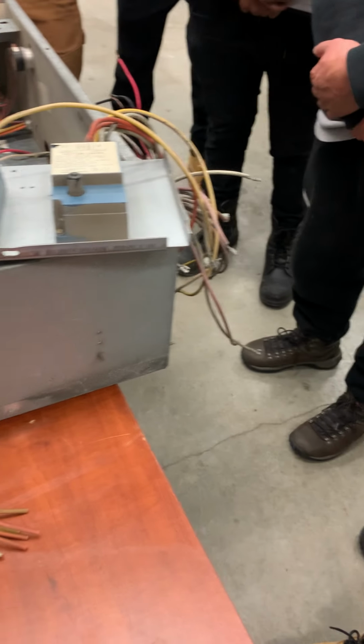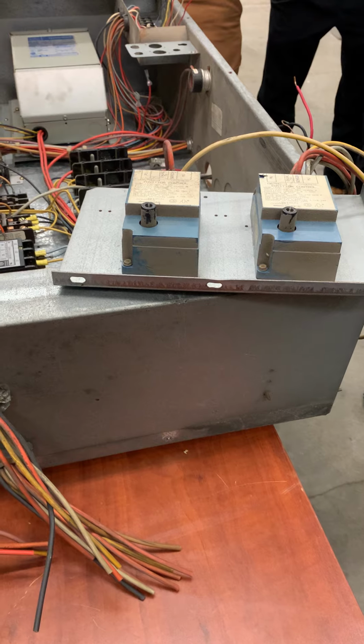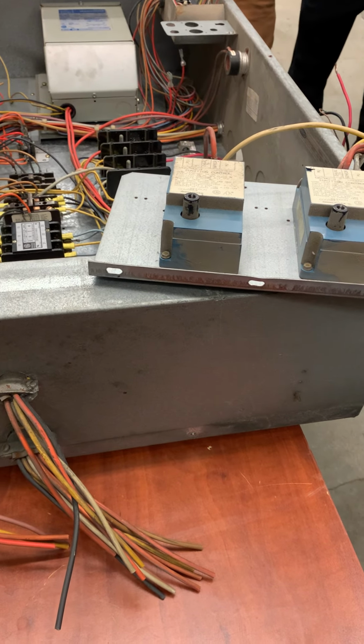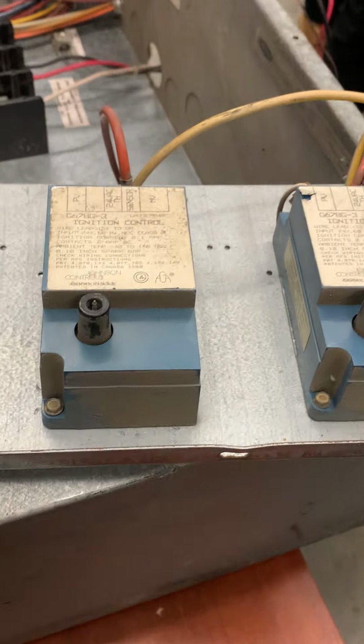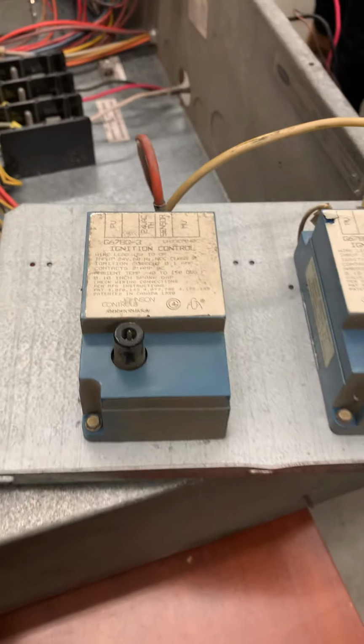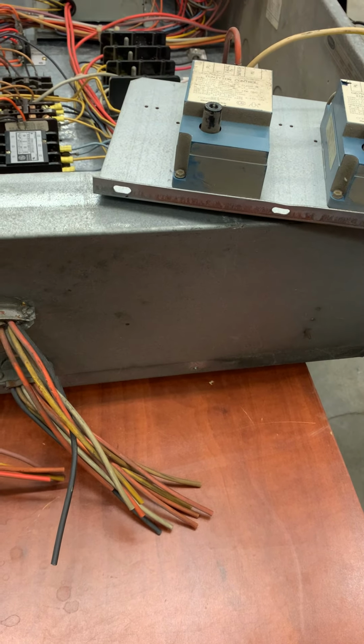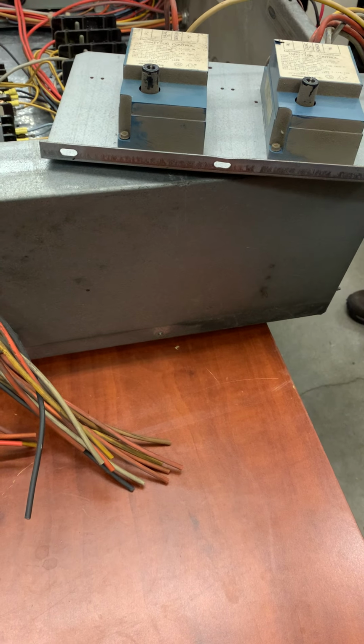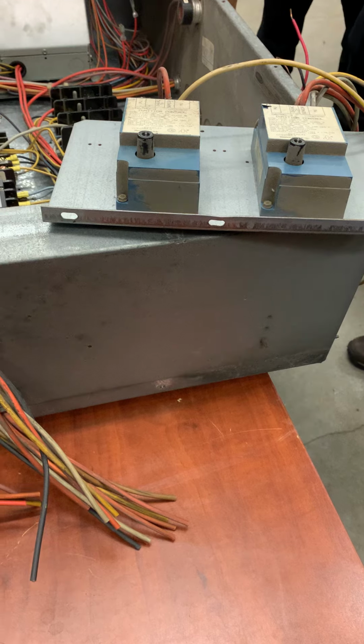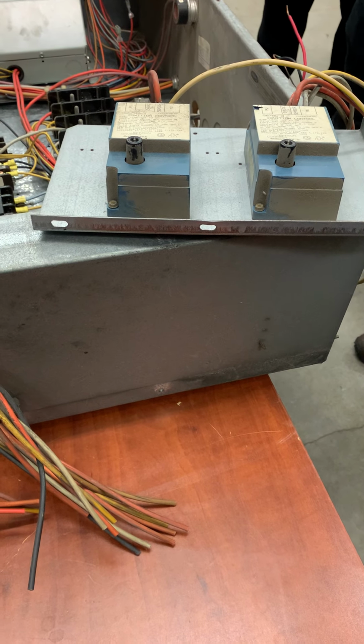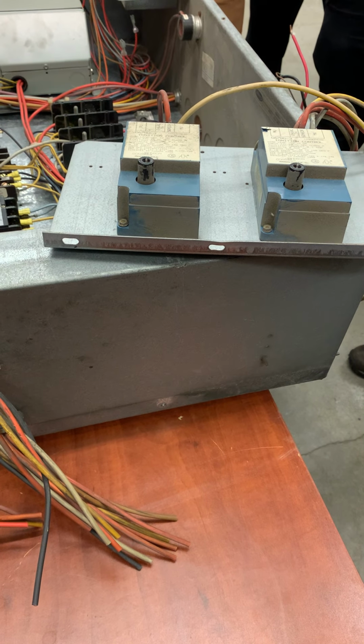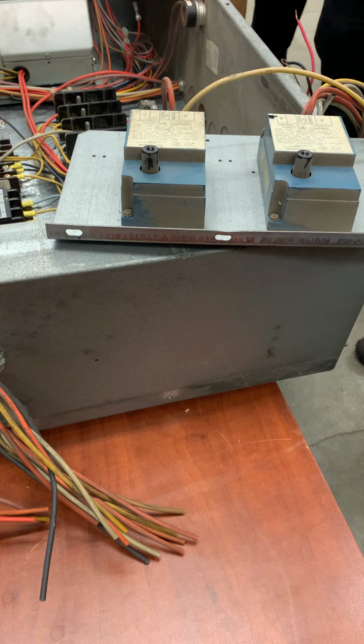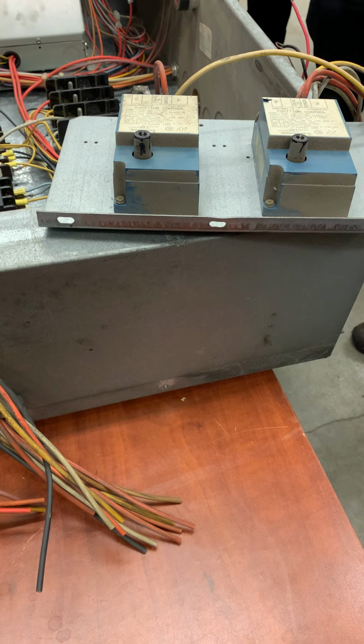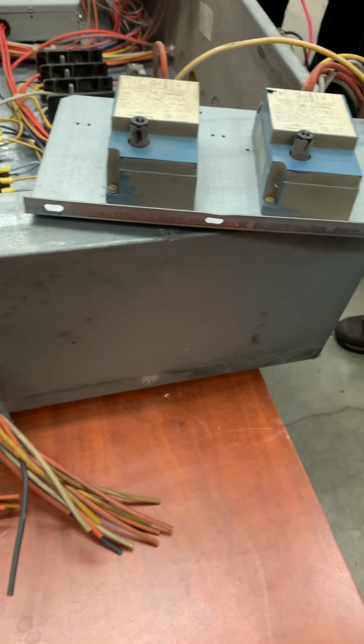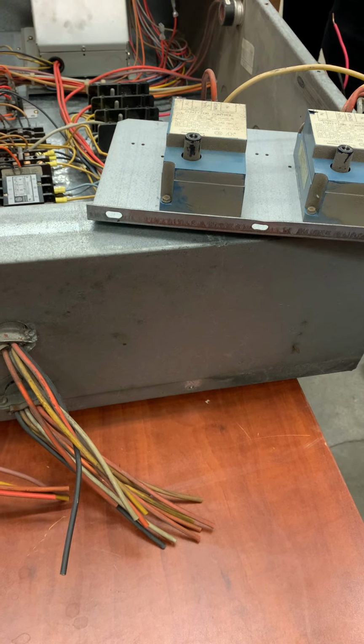Okay, can you step forward, please? These ignition controllers, tell me everything you can about them. First off, it was just a single individual component. It was the limit switch. This rooftop unit, does it have an inducer? Yes. Good. So we know it's got an inducer. Does it have a gas valve? Yes, it does. How many gas valves does it have? Two.